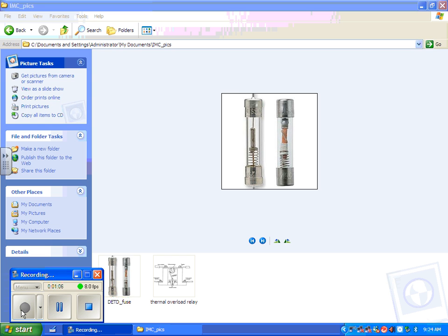But I think I've said this before, and I'm going to say it again, don't ever do that. Because if you fail to protect the motor, you get to buy it. Most likely, if you're the contractor or the foreman, and the motor fails and you did not have motor overload protection, you're probably going to wind up paying for that motor, because there's going to be a big argument about, well, you didn't protect the motor, you only protected the branch circuit. You can argue that the fuse should have protected it, but if you're at that point, it didn't, and you're going to be on the hook for buying it.